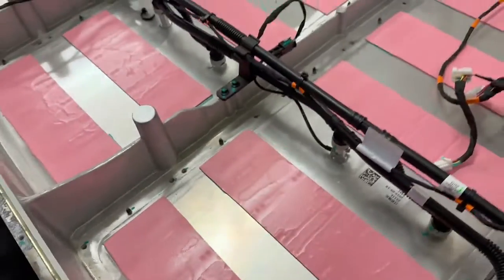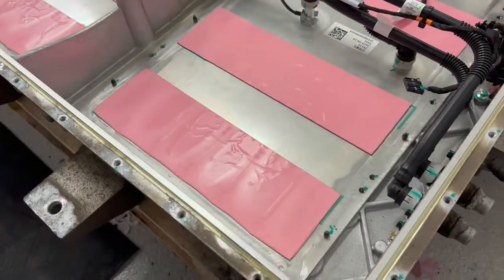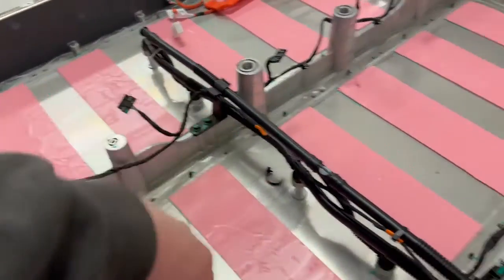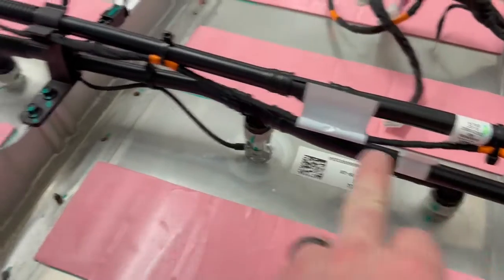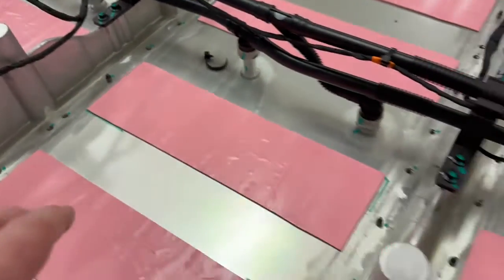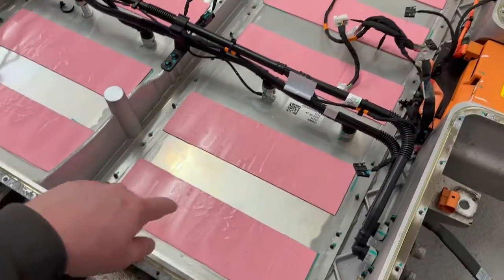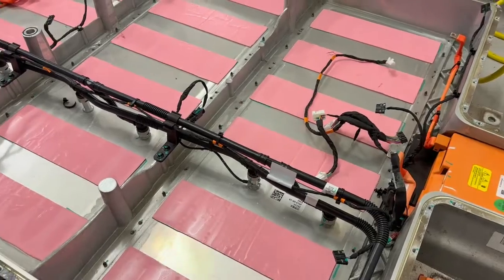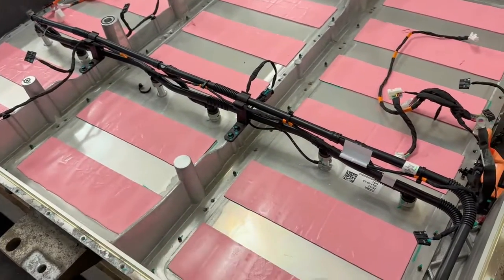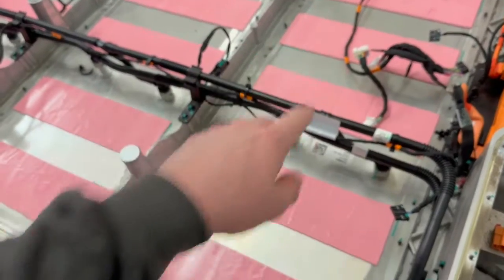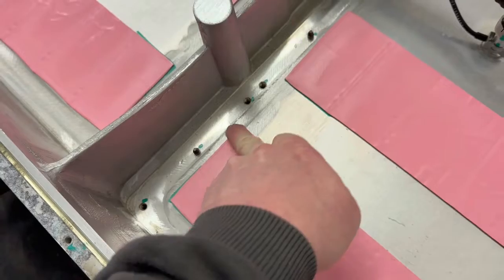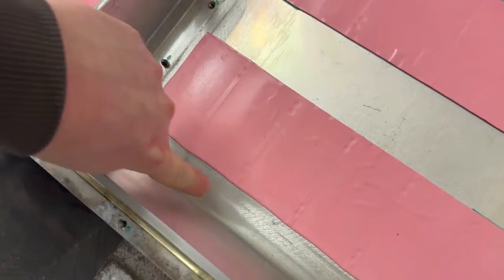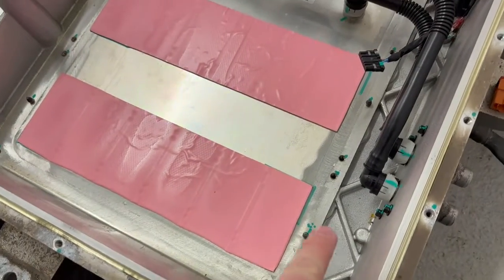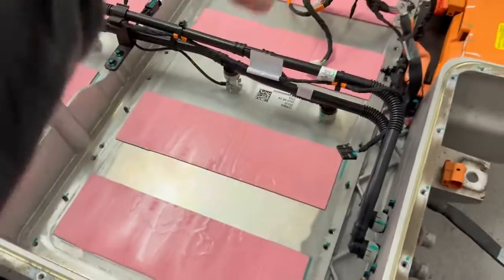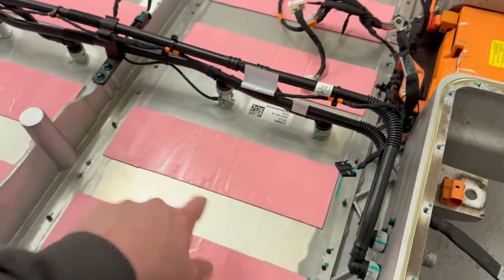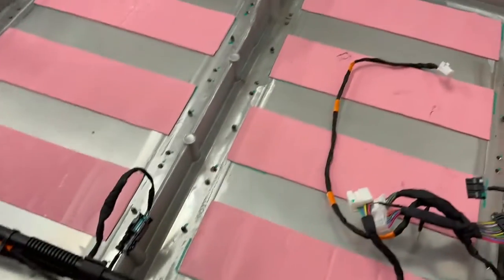So we're just having a little look at the case, and actually the solution they came up with is quite clever. It's got 3 individual cooling plates, as you can see the actual cooling lines are split and teed off here. But the way they've done it with the casting is they've cast a recess into the base of each of these 3 segments, with a cast cooling path that loops up and down. What they've actually done is put a plate in on top of it and welded that down. You can see the weld here, where they've then ground that flat to create the flat base for the batteries to sit on. So that is an individual plate which has gone in separately with the temp sensor and the cooling channel parts, and then welded in place. So it's quite neat, really.